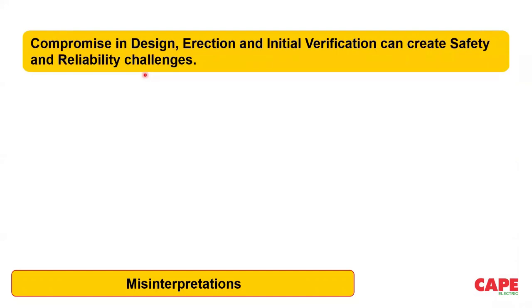So due to the reasons told in the previous slide, any compromise in design, erection, and the initial verification can create a serious safety and reliability challenge. After installation, you cannot change it, you cannot switch it off, you cannot go and test, you cannot access the wiring. So don't compromise in the design, in the erection, and in the initial verification of your electrical installation. Because if you have a perfect electrical installation, it will serve for at least 30 plus years, even 40 years.